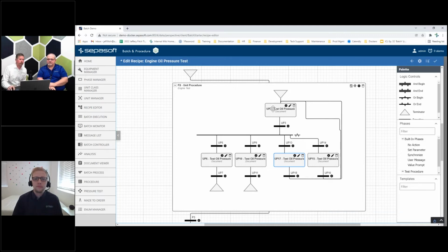So in this case here, where we have the test and these document phases, this does not use a controller at all. Over in when we did the process, then there was phase, add ingredient A. Well, that involves the controller. And in that case, yes, you would write something in the controller. So keep in mind that the controller is very good at certain tasks. And one of them is high speed cutoff of addition amounts, safety issues, all those kind of things belong in the controller. And we're not trying to replace that.